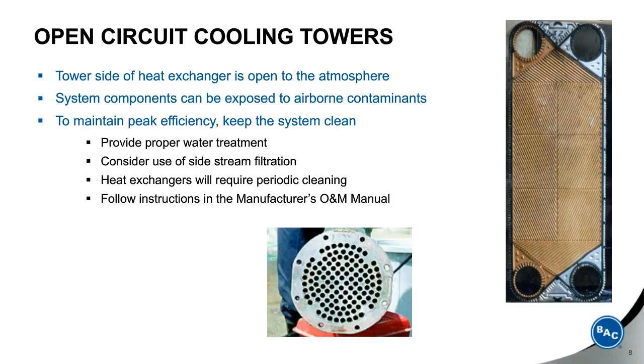For certain applications, you may want to consider the use of side stream filtration. Say your cooling tower is located near a stand of trees that could have pollen in the springtime, that could provide a load of debris that could enter the tower. So by having side stream filtration, you keep the solid content of the water down, but that also makes your water treatment program much more effective.